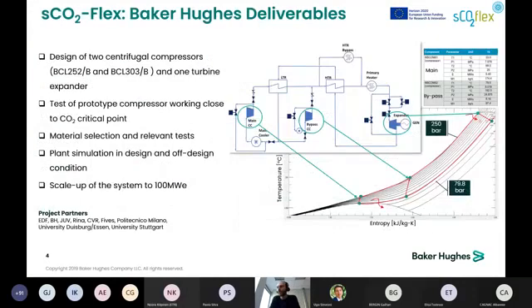As just mentioned by Albany in the previous session, the cycle selected for H2020 is a Brayton cycle with recompressing layout and flow split. So from the turbomachinery side, we have 2 compressors, the main one and the bypass one, plus an expander turbine. Both compressors operate between 80 and 250 bar, but the main one in particular is operating very close to the critical point, where thermodynamic quantities are characterized by large gradients.